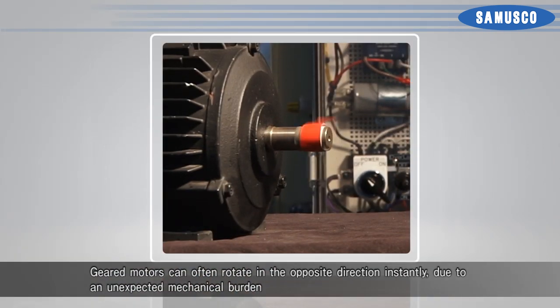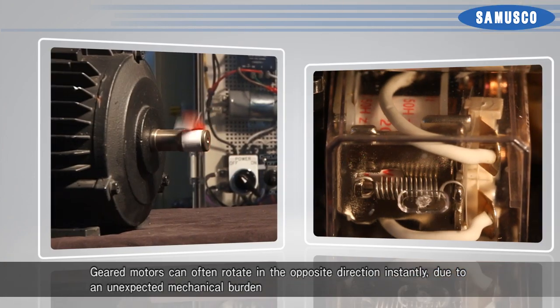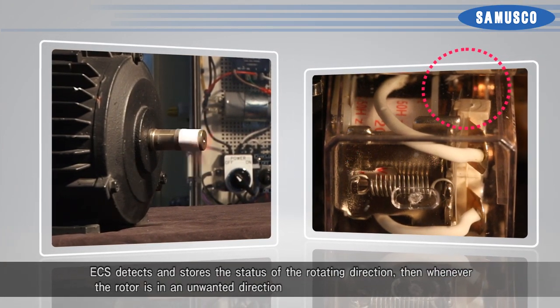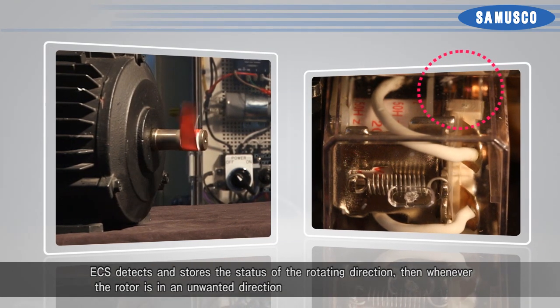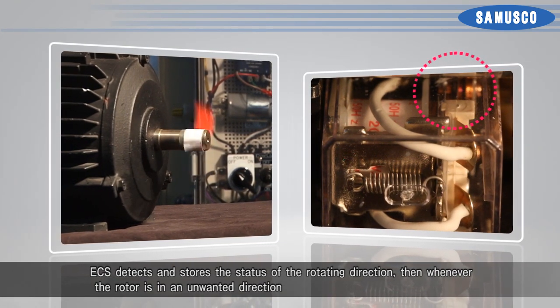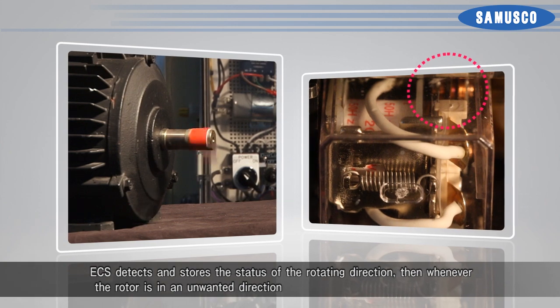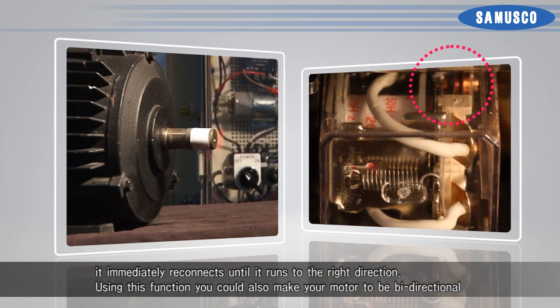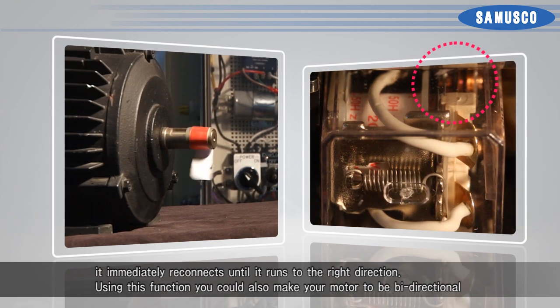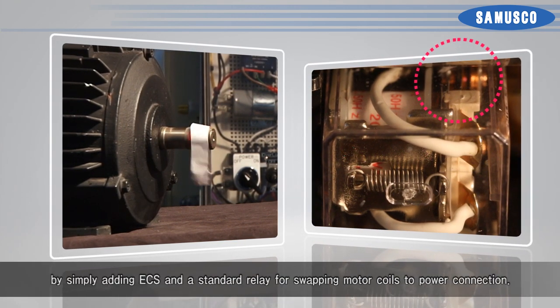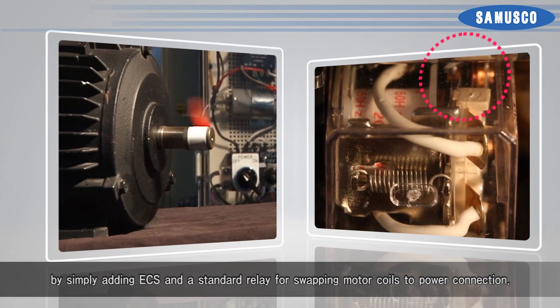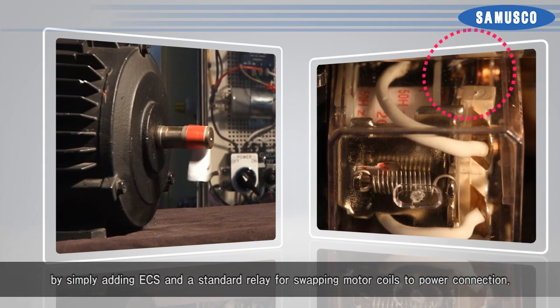Geared motors can often rotate in the opposite direction instantly due to an unexpected mechanical burden. ECS detects and stores the status of the rotating direction. Whenever the rotor is in an unwanted direction, it immediately reconnects until it runs in the right direction. Using this function, you could also make your motor bi-directional by simply adding ECS and a standard relay for swapping motor coils to the power connection.